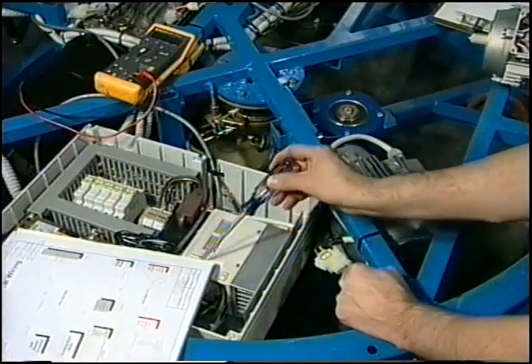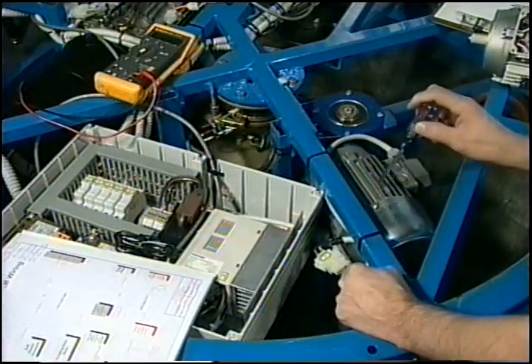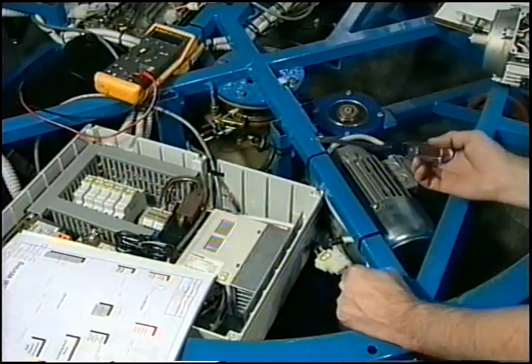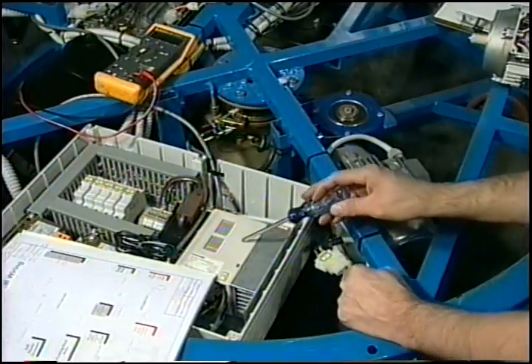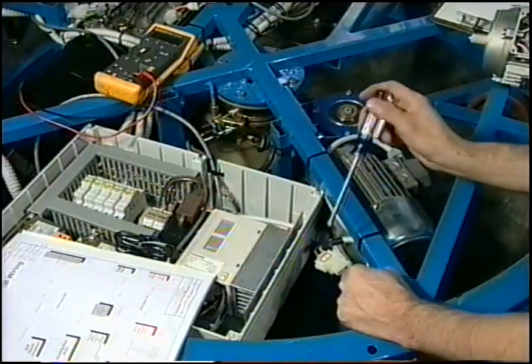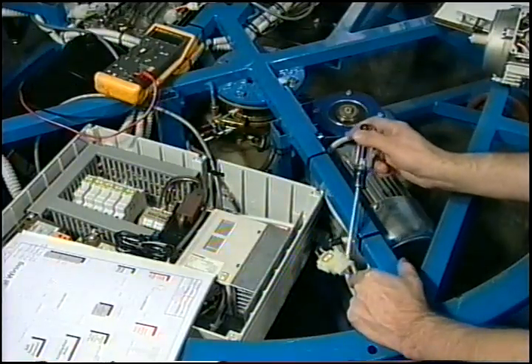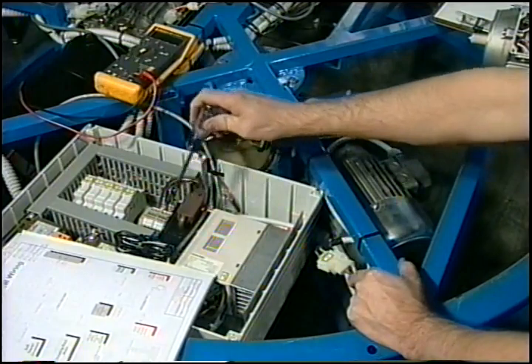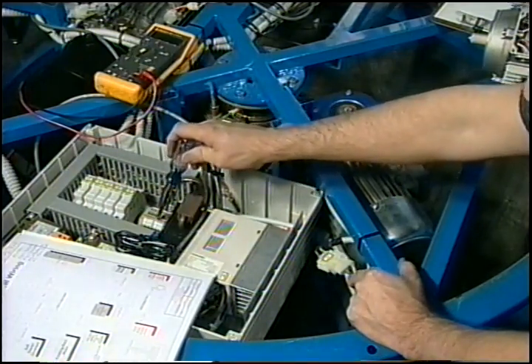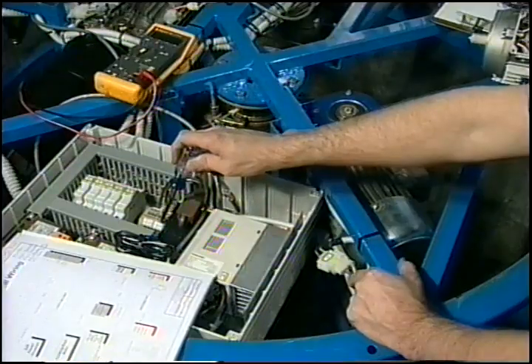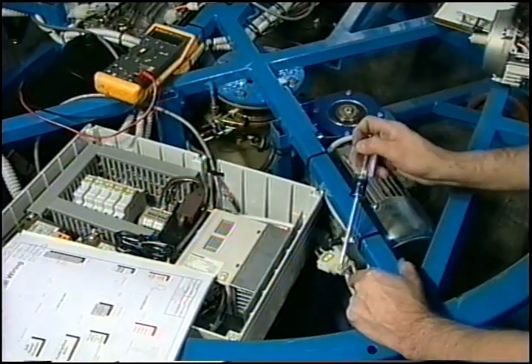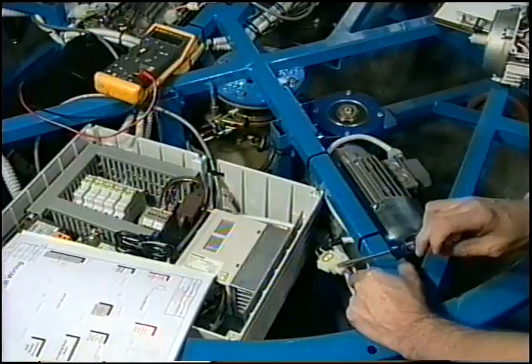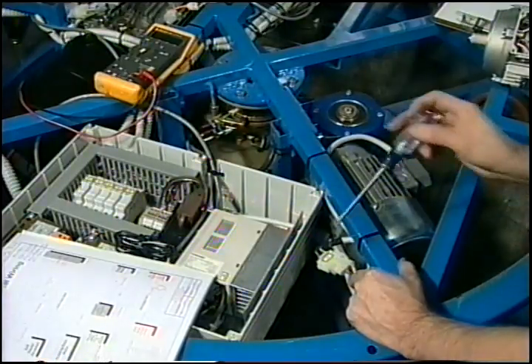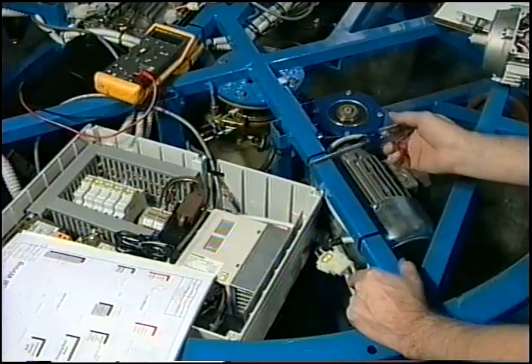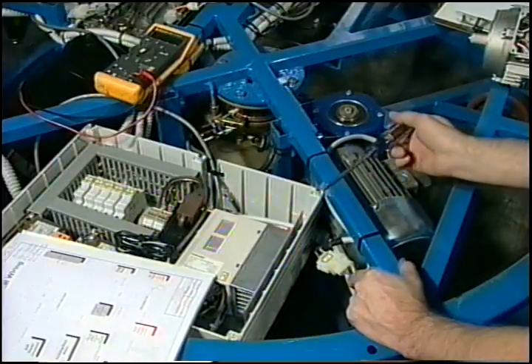Your Toshiba transistor inverter operates your rotation motor. When you're testing this and you're going through that command mode that we talked about earlier, if you want to check voltages here, the best way is to put 1 lead of your meter on the neutral line here, take your other lead and place it inside the wire, making contact to the pin itself. It should read anywhere from 170 to 180 volts AC.